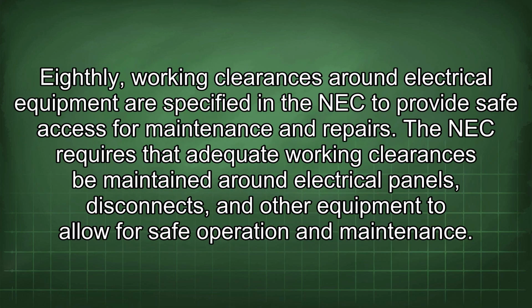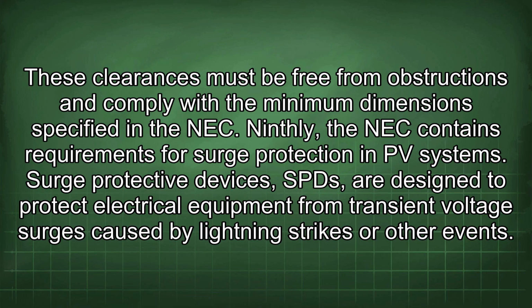Eighthly, working clearances around electrical equipment are specified in the NEC to provide safe access for maintenance and repairs. The NEC requires that adequate working clearances be maintained around electrical panels, disconnects, and other equipment to allow for safe operation and maintenance. These clearances must be free from obstructions and comply with the minimum dimensions specified in the NEC.